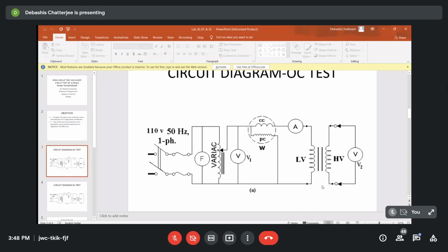If the series element magnitudes are high, meaning high leakage reactance and resistance, then since the load current flows through them, high resistance means high losses. Second, high impedance means high voltage drop, so the voltage available at the load point will be lower. Naturally these elements are of very low value compared to the shunt elements.